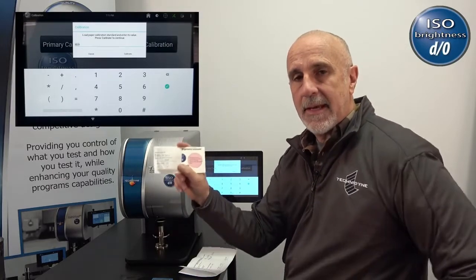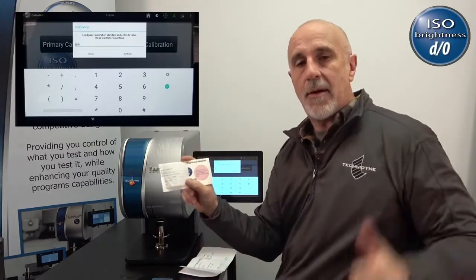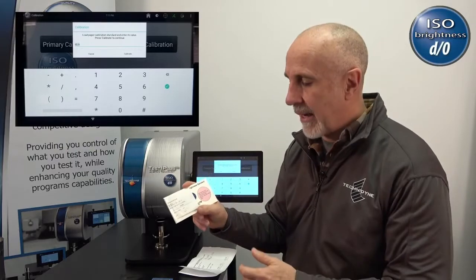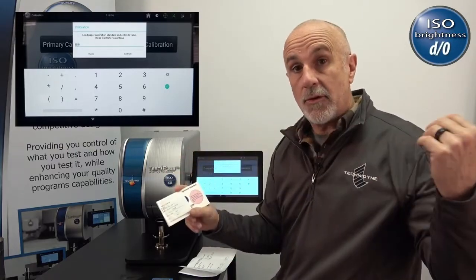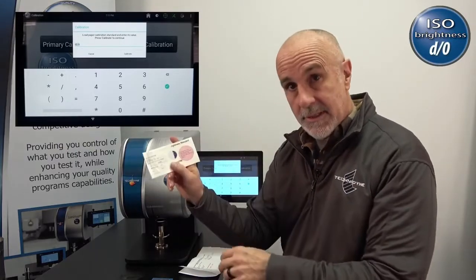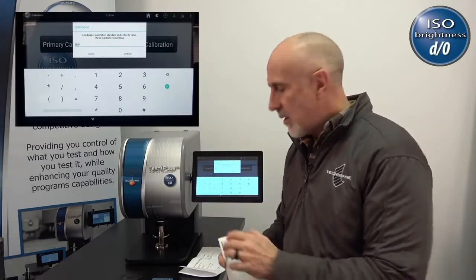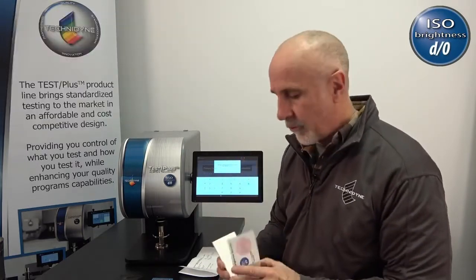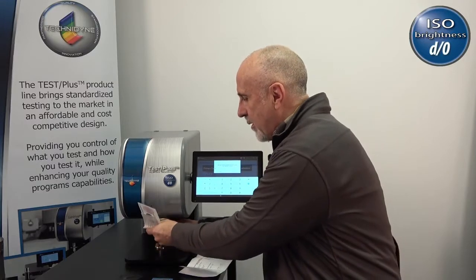Now this standard, like all the standards, has been evaluated on our master instruments back in our laboratory. And a value is assigned based on the reading from that master instrument. For this standard, the value is 90.9. So I will enter that value into the software. I will load the standard onto the instrument.